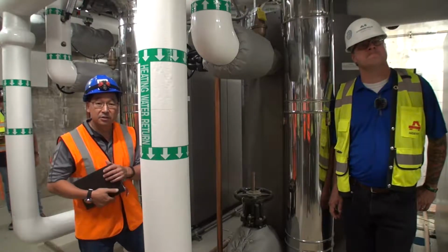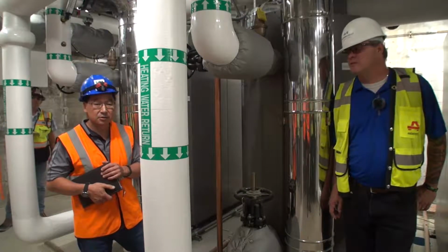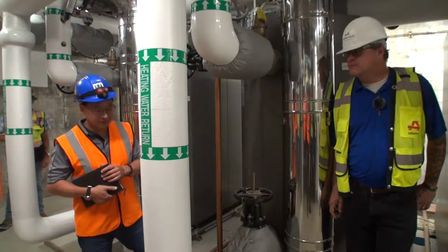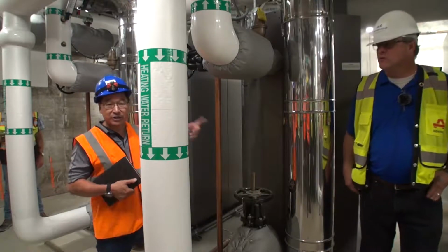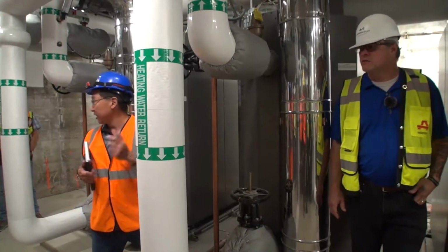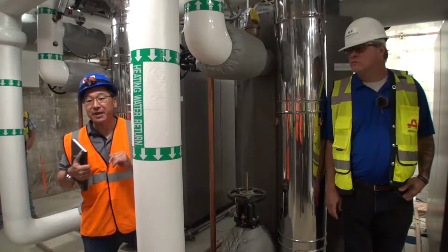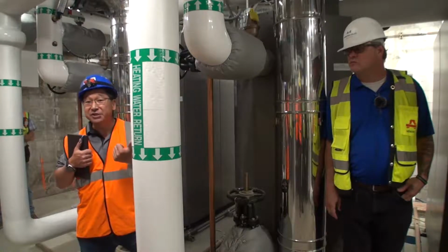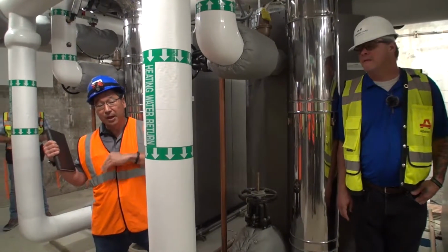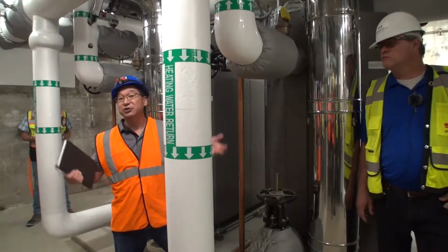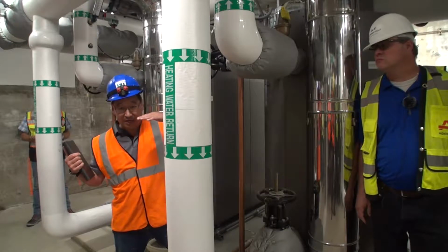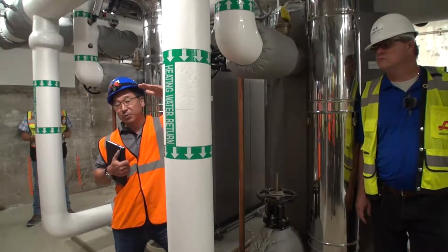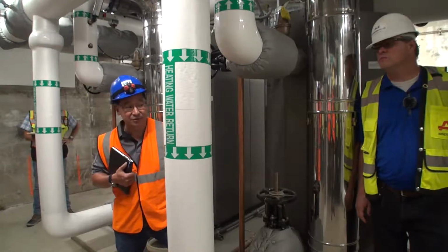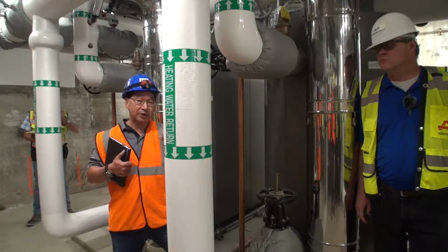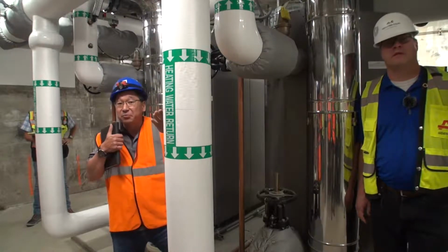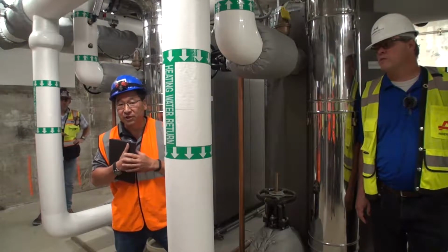So are you saying that we never should lock that down, and if we do, what should we do to avoid that problem? If, for instance, you have to lock it down, you could put these 2 in a manual mode, and we can go over that if you guys see fit. Right now, the energy management control is sending what we call a reset signal, an outdoor reset, based on outside air temperature. The colder it is, the more energy is needed in the system, right? So the energy management will raise that set point. As it gets warmer, it'll lower that set point, basically for efficiency. We can put a boiler in manual mode and it'll just operate at a fixed set point, be it 160, 140, what have you. That's possible. We can go over that.